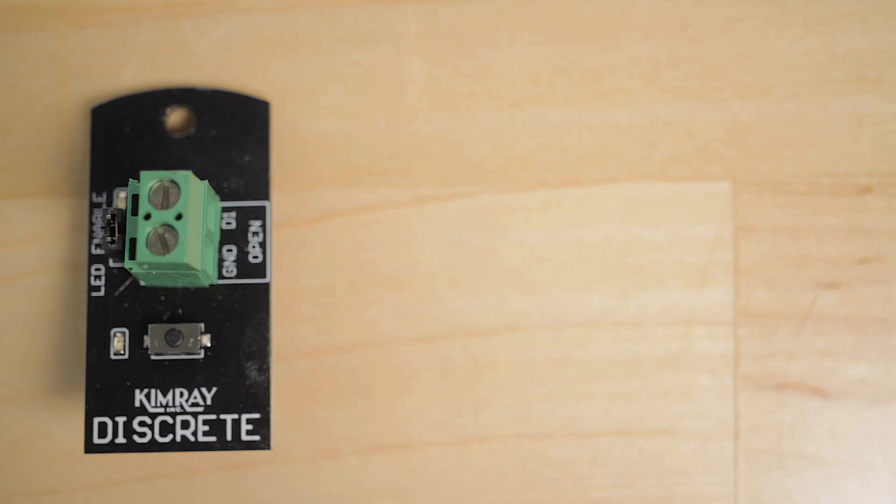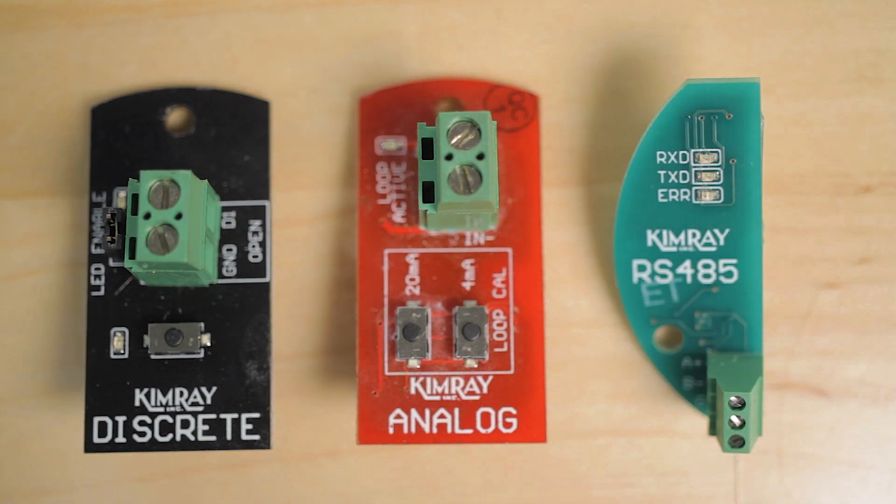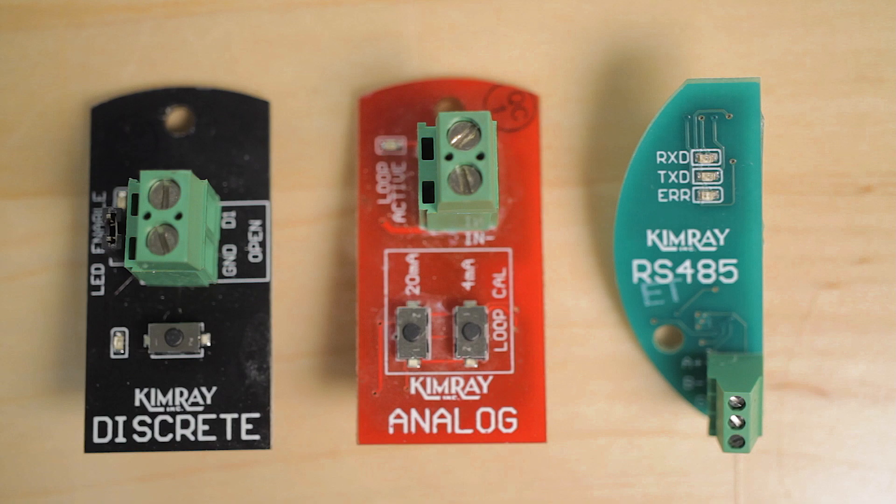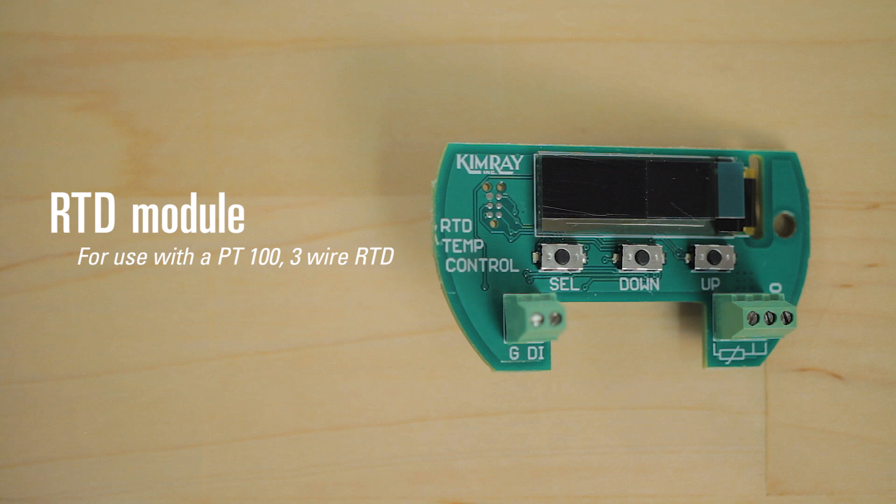A discrete module which uses dry contacts only, operating on less than 3 volts, an analog module which is 4 to 20 milliamps for variable control, and a Modbus control module for Modbus RS-485. Coming soon we also have an RTD module for use with a PT-100 3-wire RTD.